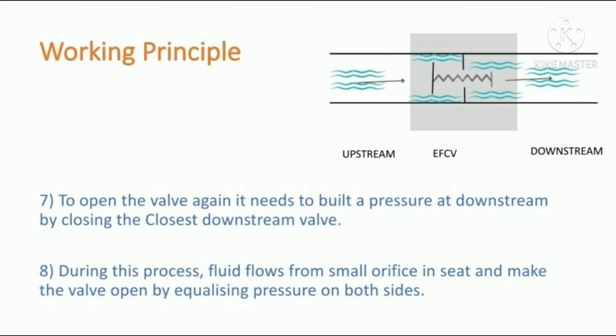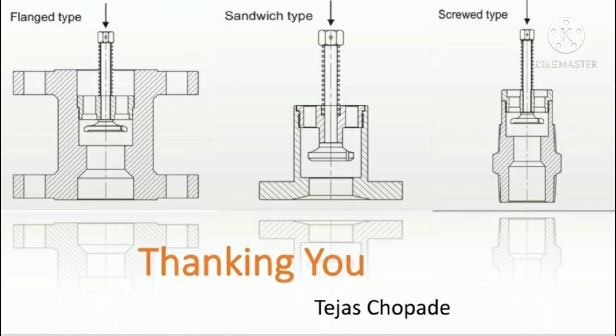To open the valve again, it is necessary to build up pressure at the downstream by closing the downstream valve. During this process, fluid flows through a small bore in the seat and equalizes the pressure on both sides, causing the valve to open again.